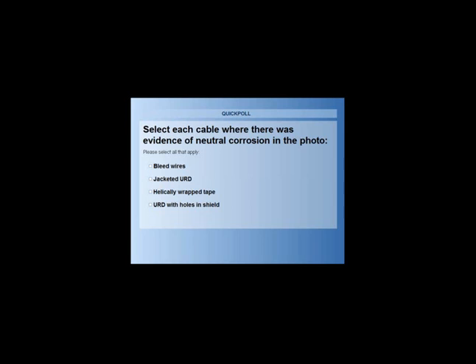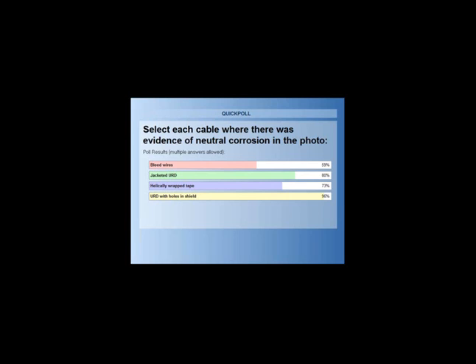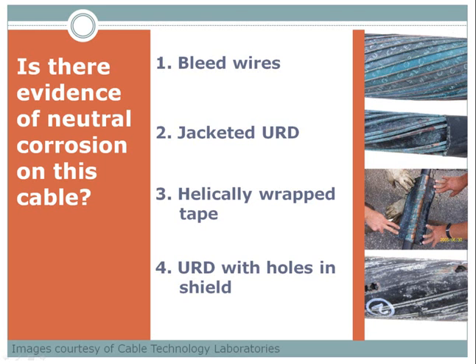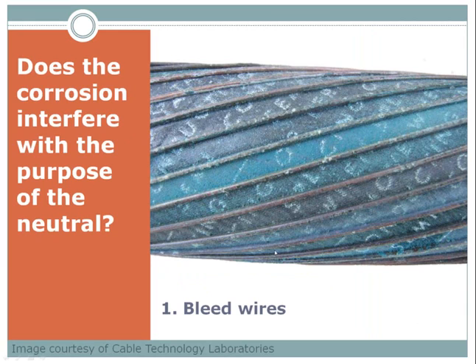People clearly understood the last one had a corrosion problem, especially with the hint. But some people couldn't see the evidence in the first three cases — typically 20 to 30% missed it. All four of those have evidence of neutral corrosion. You probably thought it was a trick question. Because here is the question you might have been answering: does the corrosion interfere with the purpose of the neutral? So now I want you to give me four new checks.